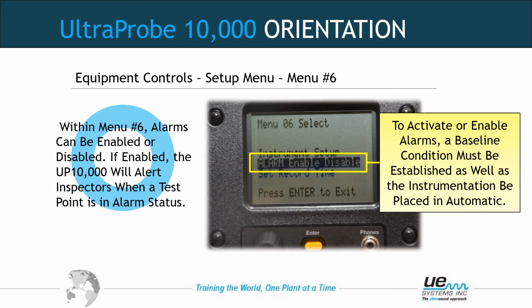To activate or enable the alarms, a baseline condition must be established, and the instrumentation must be placed in automatic. So the instrument setup should be in automatic, so it will read the information from the software and what those alarm values are. Then you can enable the alarm. If you don't like that feature, turn the alarm off. If you're not going to do anything if it does go into alarm, you're going to wait until you see the DMS software and then run a report, then turn the alarm feature off. It's not needed.